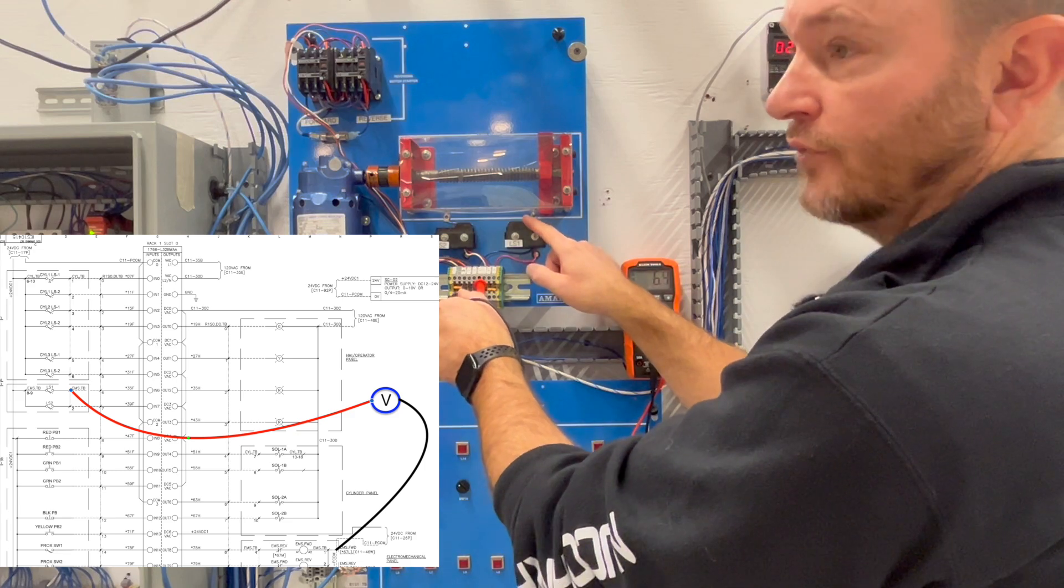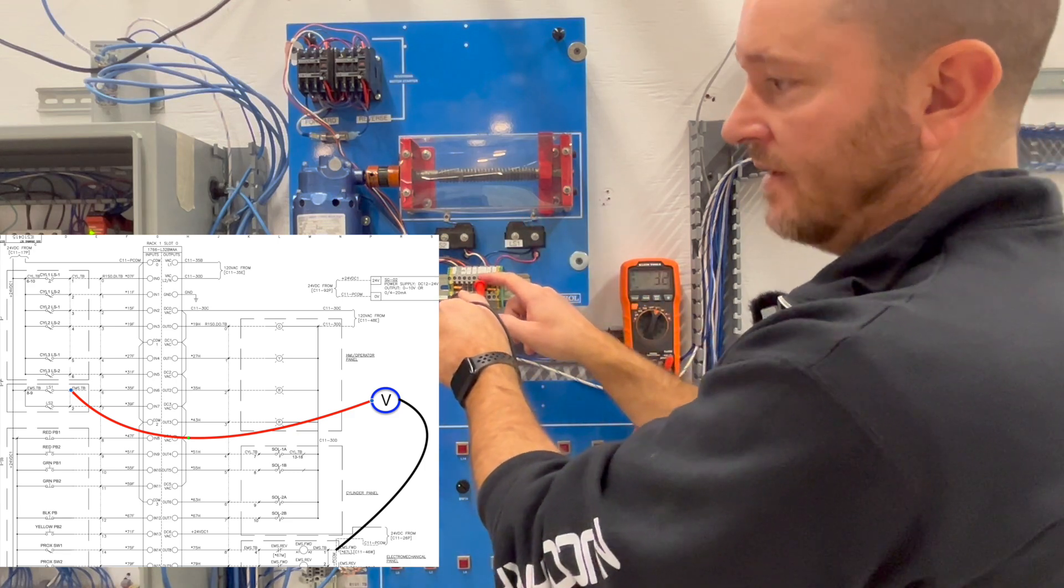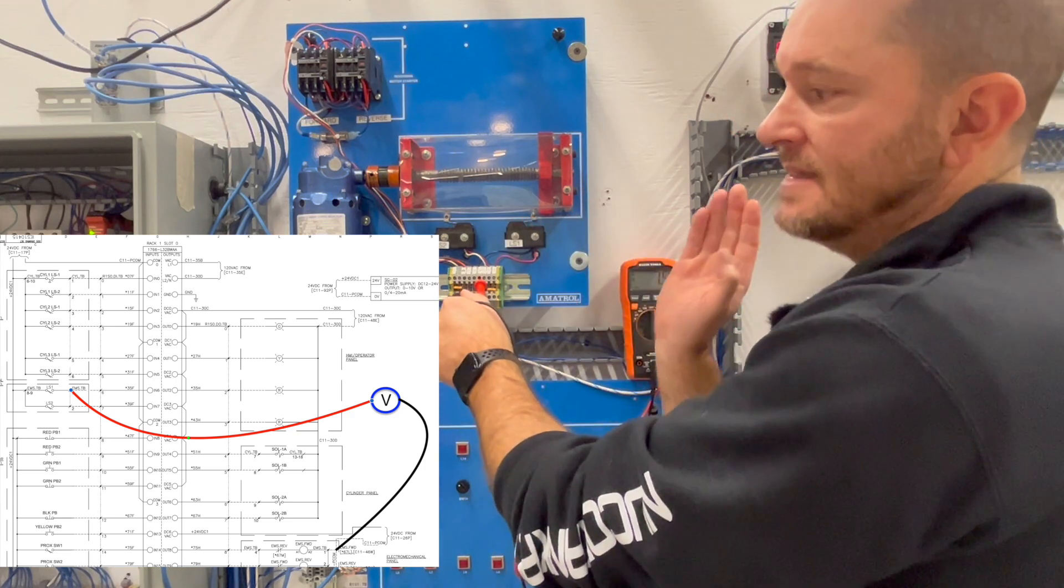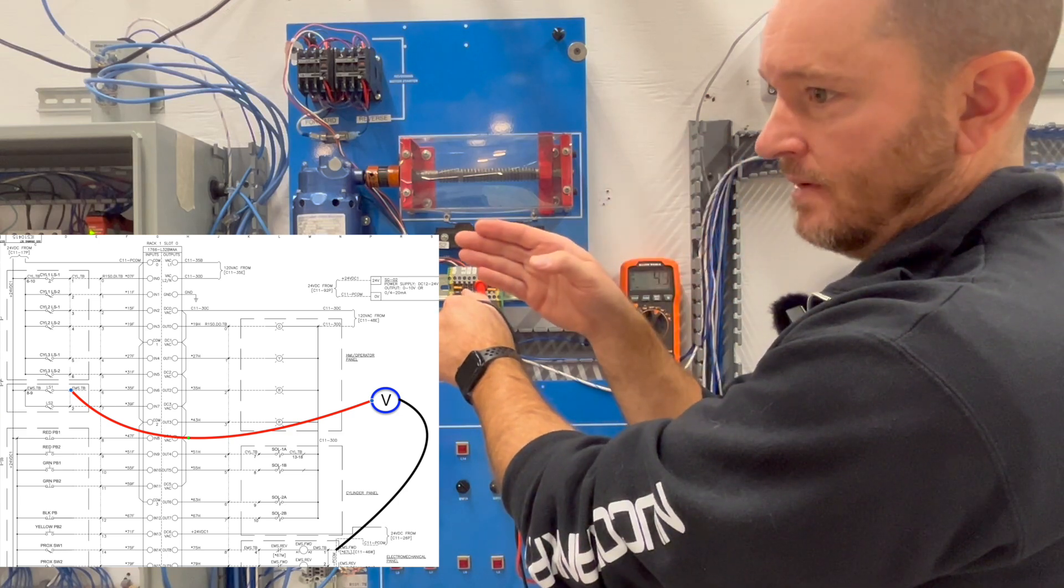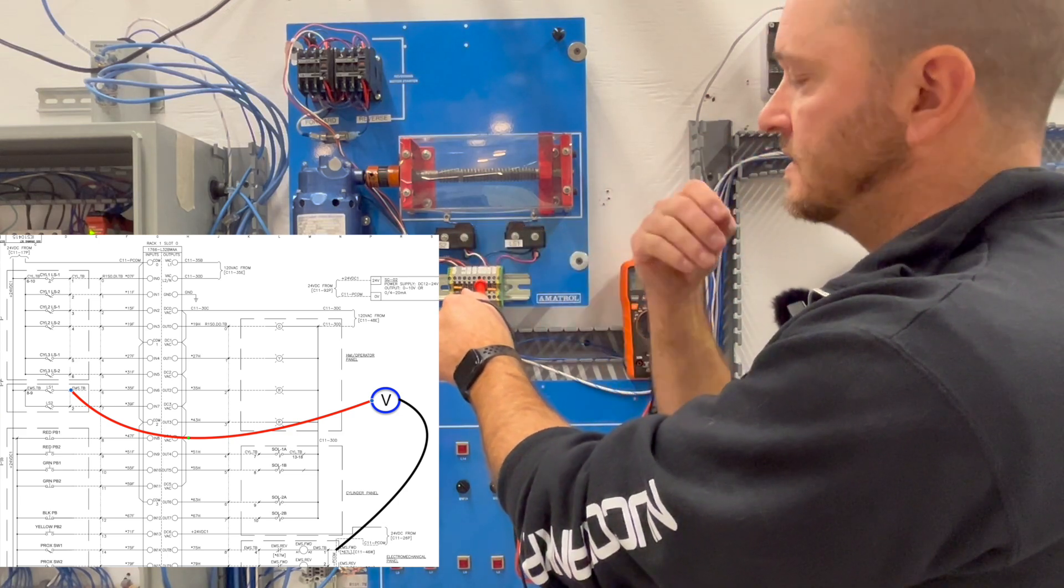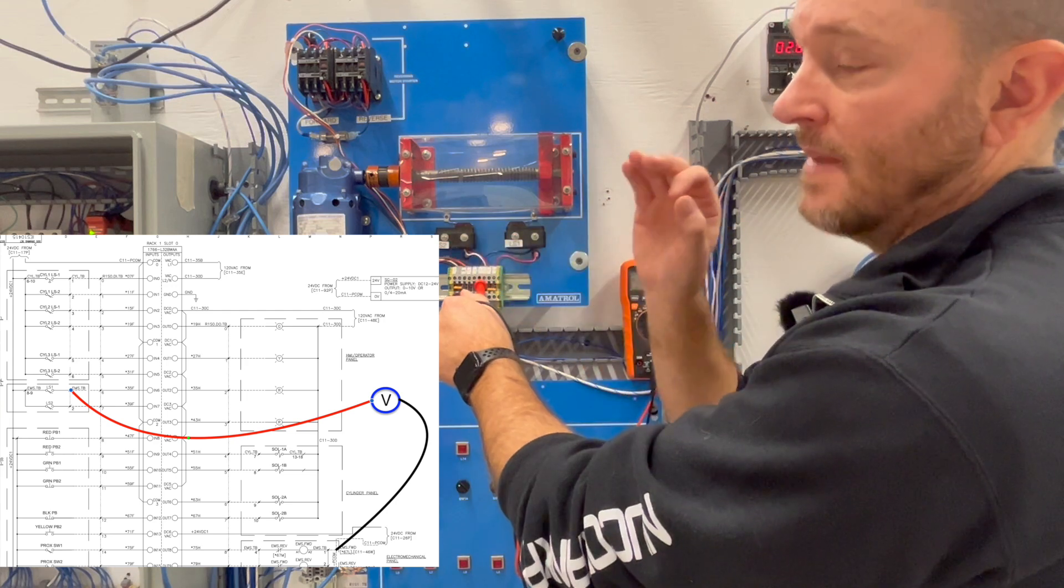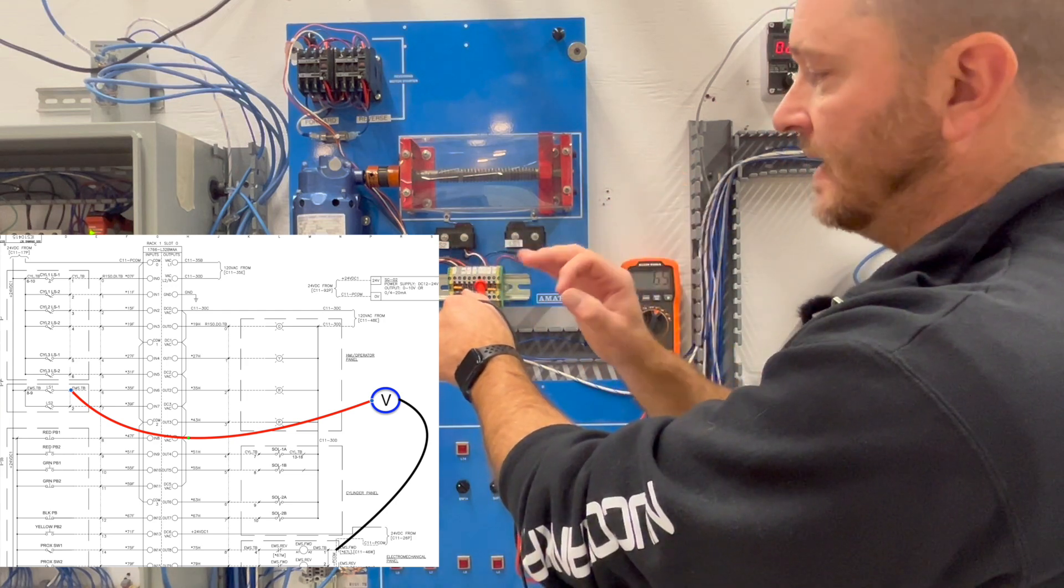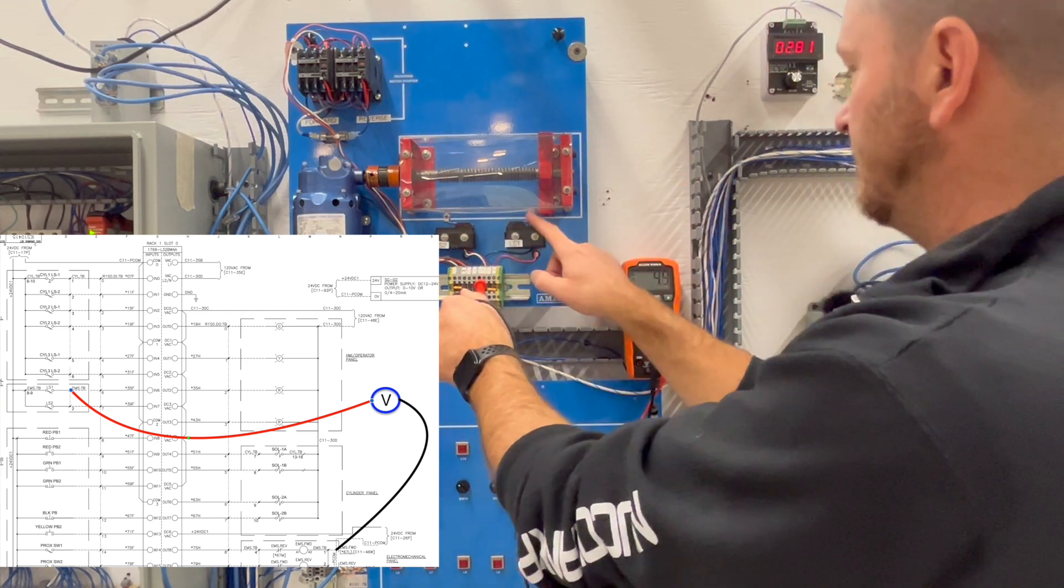Now if I am getting voltage here the problem is then downstream. Okay something's unhooked, there's a wire loose, maybe my input's gone bad, something like that. But in this case hopefully you can see this, we are not getting 24 volts.